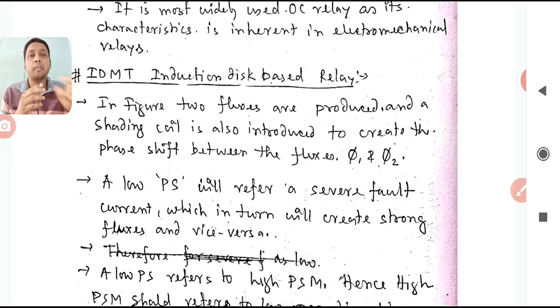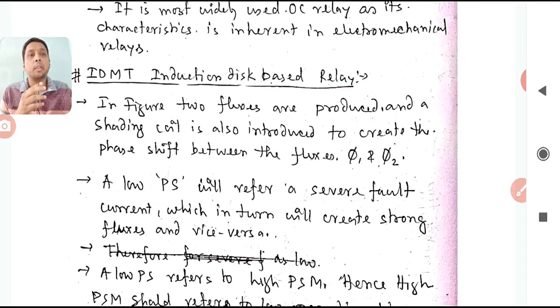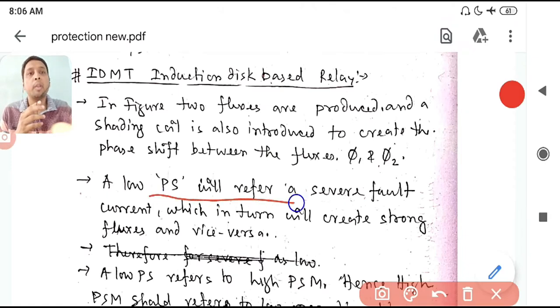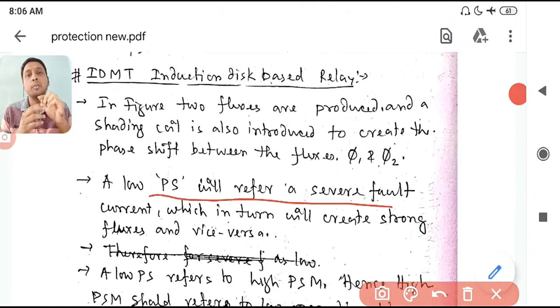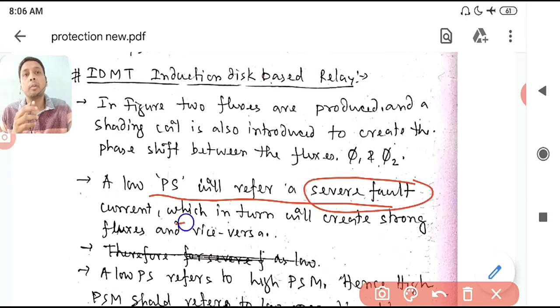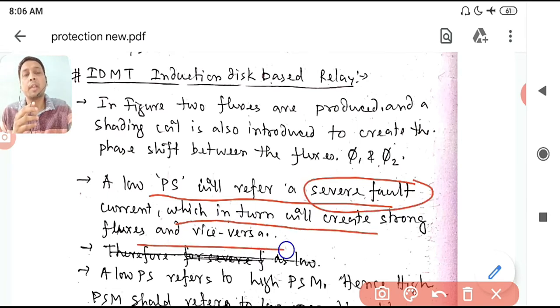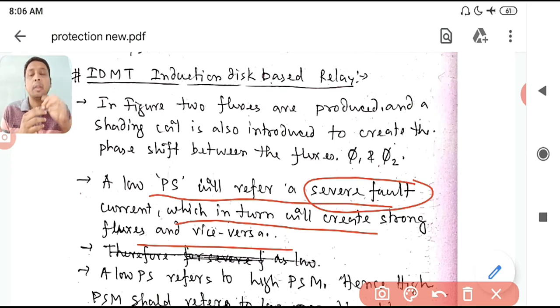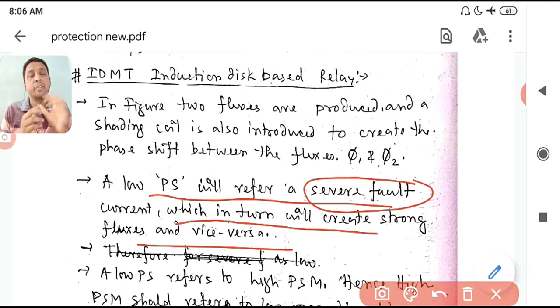First, consider what is low PS. Low PS means you are setting a very small threshold value. For a fixed fault current, a low PS will make it look like a more severe fault current, which in turn creates a stronger flux. More current means more flux.